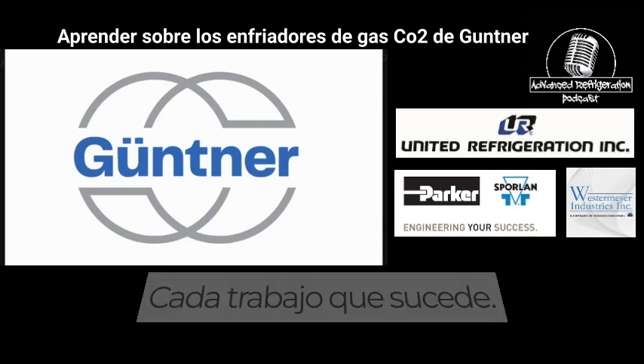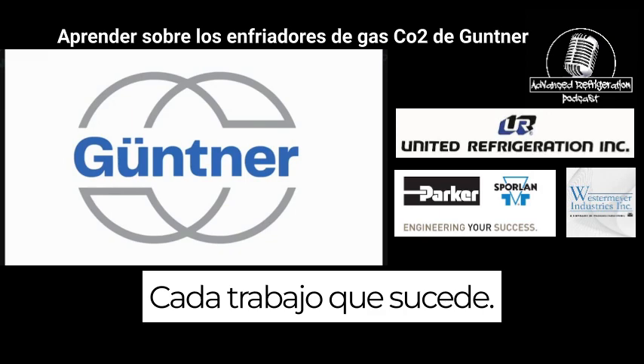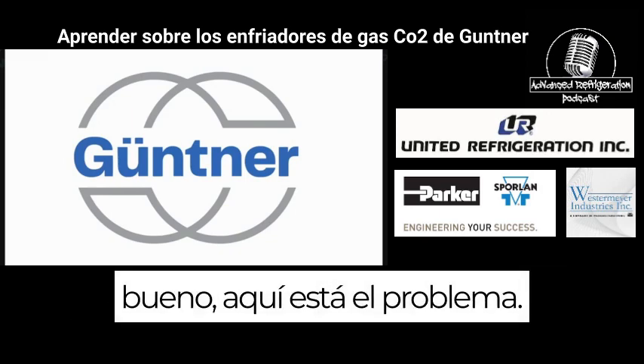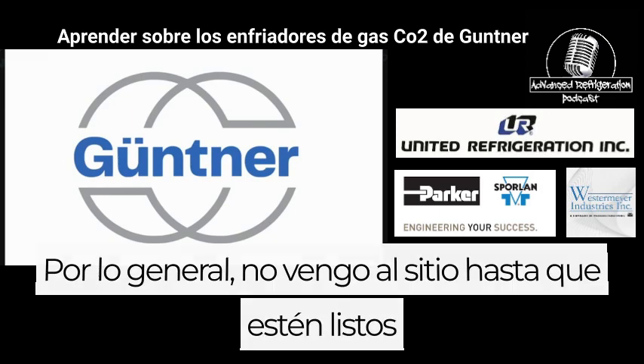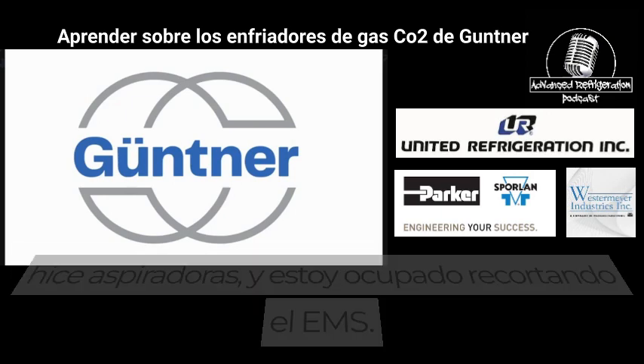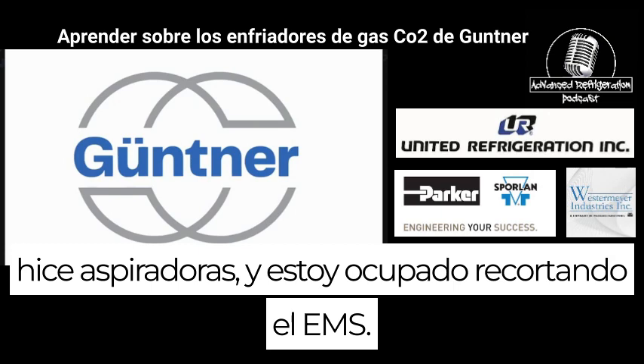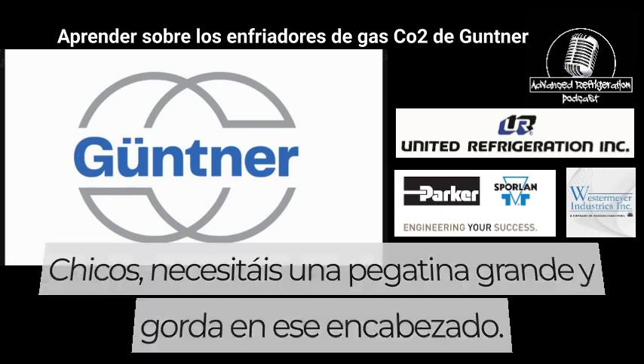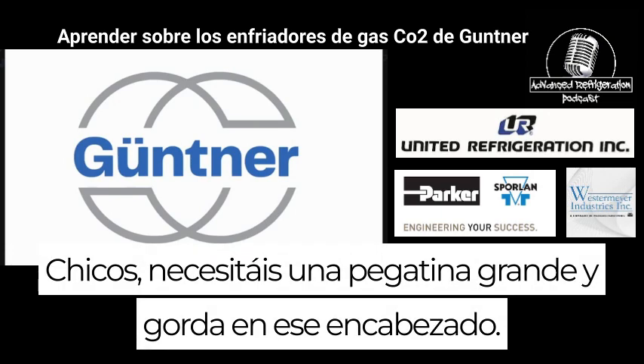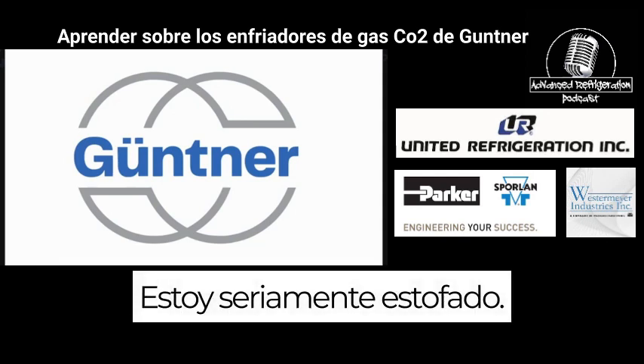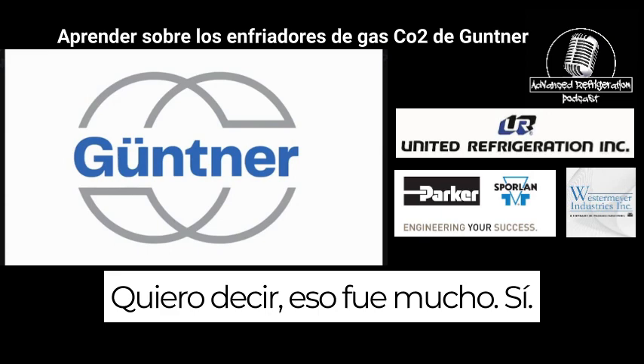See, this happens every single job, exactly what you said. Here's the problem: I do startup. I generally don't come on site until they're ready to do startup, and by that time they've already pulled vacuums and I'm busy trimming out the EMS. You guys need to put a big old fat sticker on that header. I'm serious. That well must be brazed in. I mean, that was a lot of it.